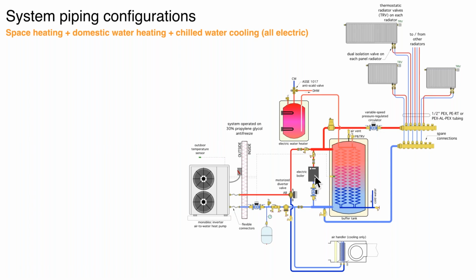And in this case, I'm showing an electric boiler simply piped in parallel with the heat pump as a booster or as a backup. So if the heat pump capacity is insufficient on a very cold winter day, the electric boiler can come on. Again, some heat pumps have internal controls that can automatically provide a contact closure to signal the auxiliary boiler to come on.